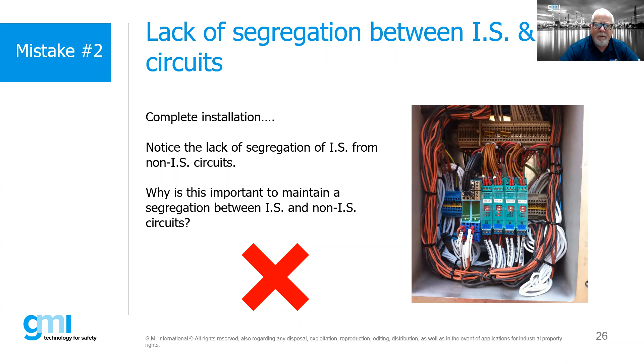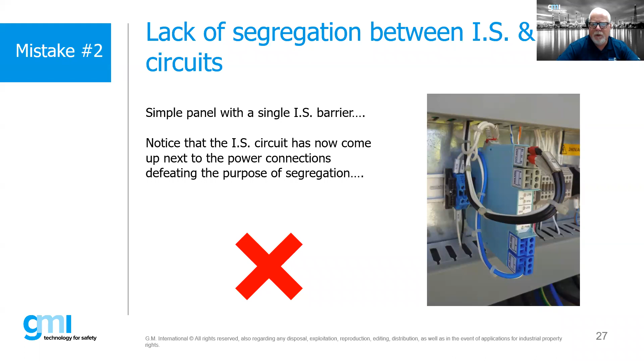Now here's an example of just a simple single barrier. And again, we look at the power cables that are coming into the barrier at the top versus the outgoing IS. Again, it started off fine where the connections were made, but then we've run those cables right next to each other. So we have to make sure that we keep a separation of 50 mm between our IS and non-IS with all of our wiring. This is one of the things that as a designer, you can design it, but if the contractors or the field technicians aren't installing it properly, then it somewhat defeats the purpose. And this is one of the biggest issues that we also see, besides the ground.